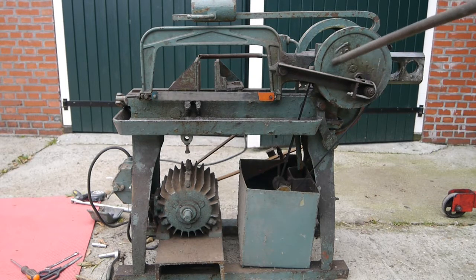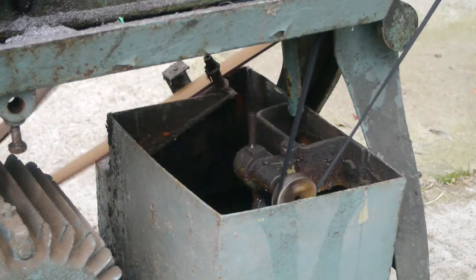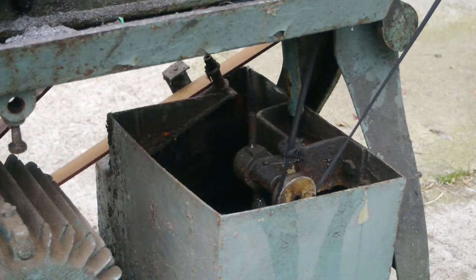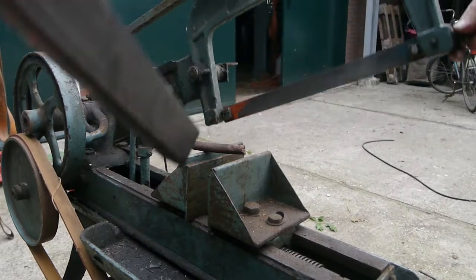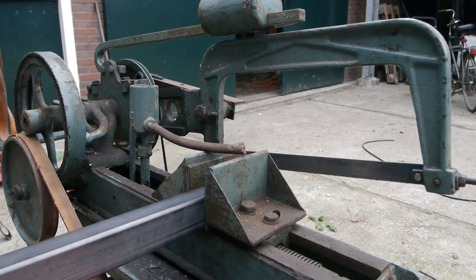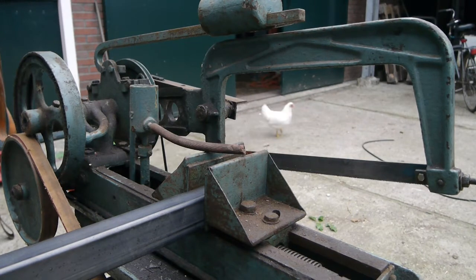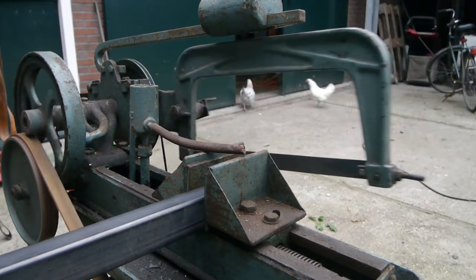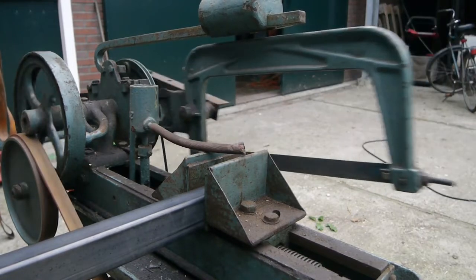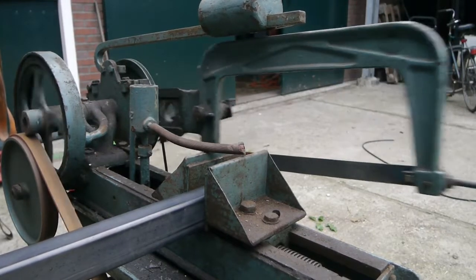There's an arrow there showing the direction. I'm curious if this pump is still doing anything — that's not doing anything. The belt is slipping. I really need to tighten that belt — that belt is not going to be fine.